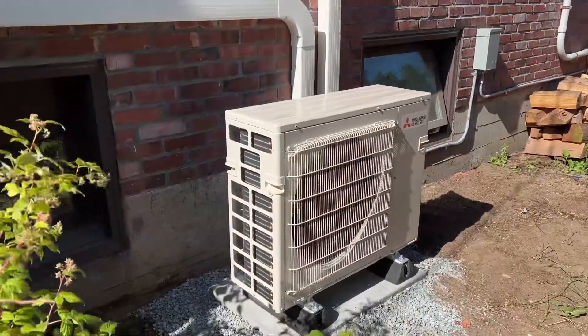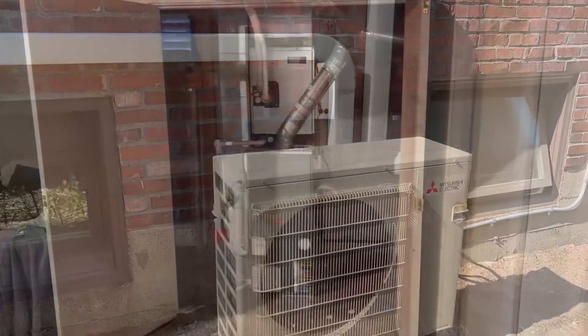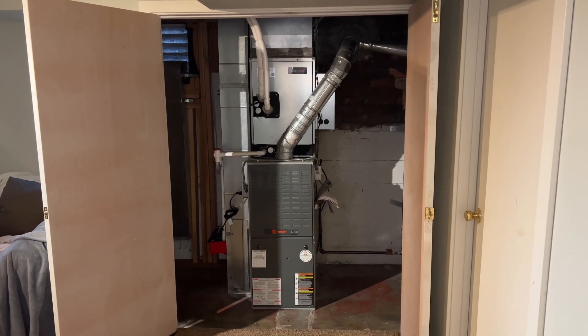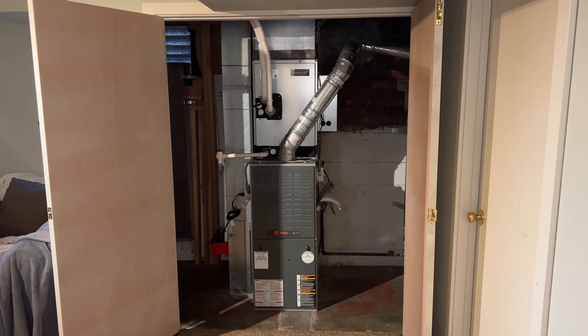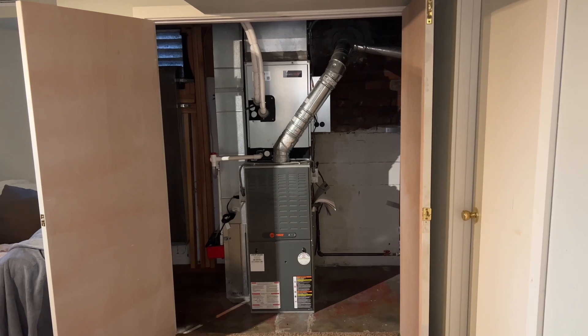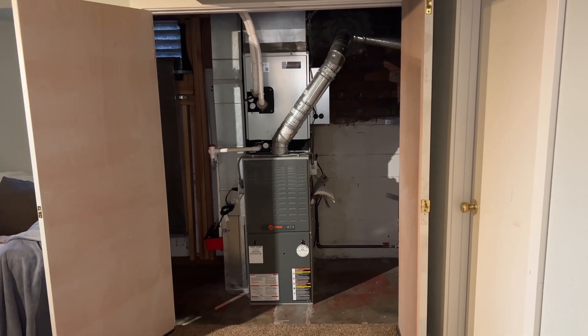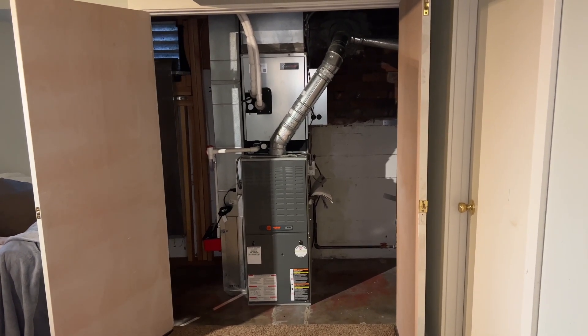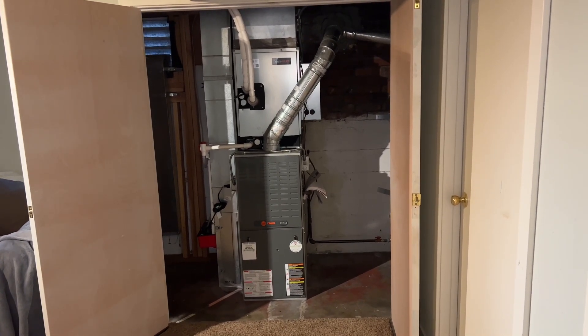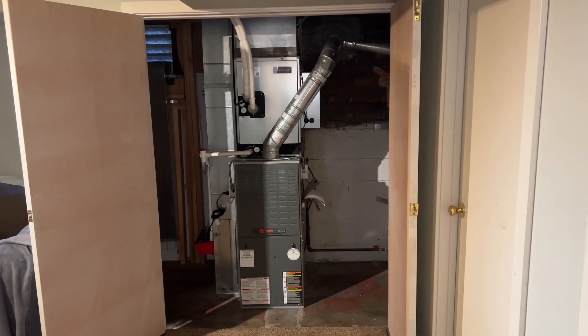This is a Mitsubishi heat pump with an IntelliHeat gas furnace backup. Here's the inside component — we have an existing gas furnace with the Mitsubishi IntelliHeat on top of it. This is super awesome because now we can add a mini split head upstairs, which we couldn't do before. Otherwise you'd end up with two standalone systems or have to replace this with an air handler. This reduces cost, gives you a gas backup instead of all-electric or hyperheat equipment, and lets you run a dual fuel system for better overall comfort.